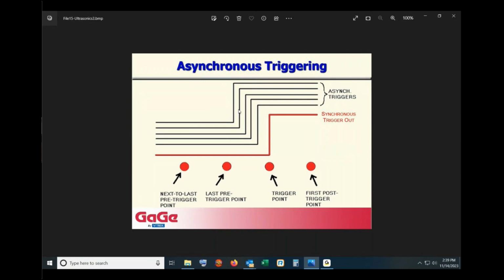Since the triggers are asynchronous to the sampling clock, on successive acquisitions they arrive with different phases with respect to this trigger point. So here I've drawn 5 different black triggers that occur on different acquisitions, but those would all be logged as this trigger point, because that's the next clock edge after the trigger occurs. Basically, the card can't tell the difference between these 5 external triggers.